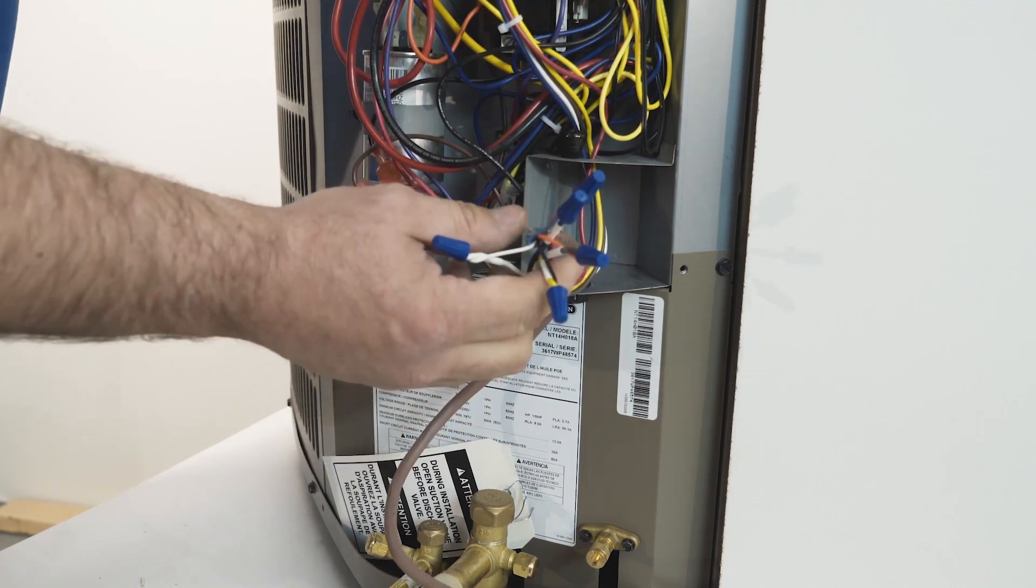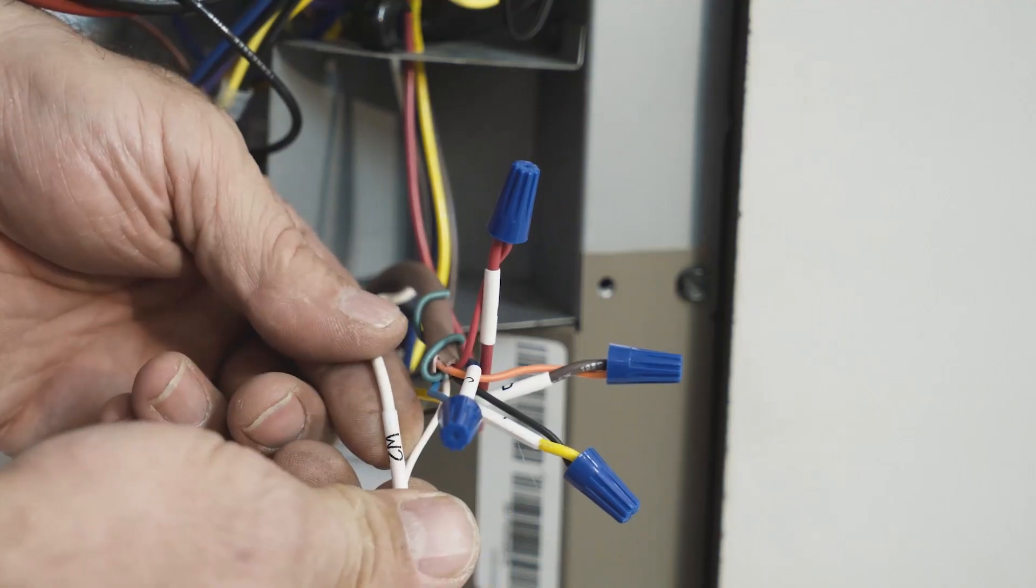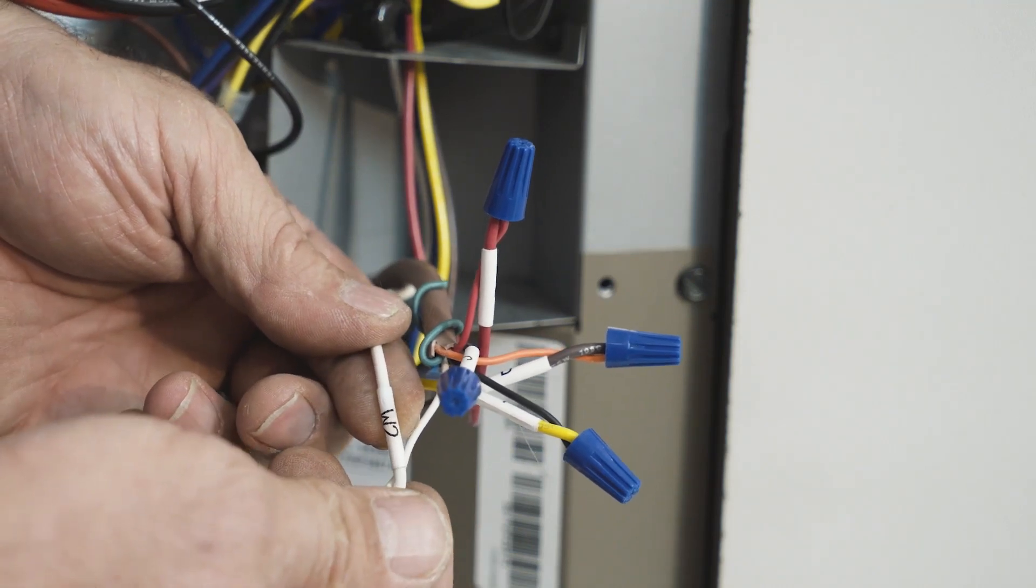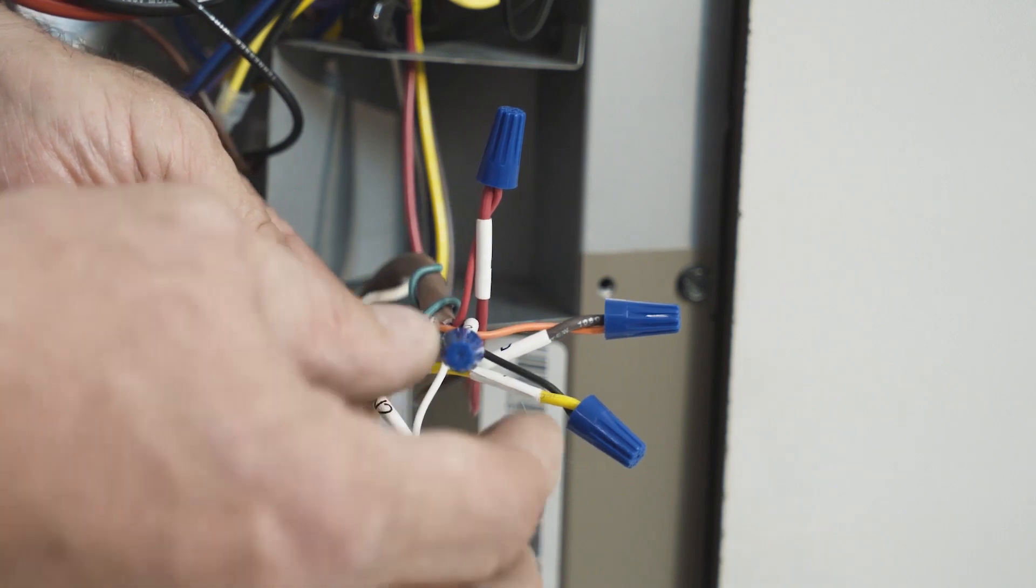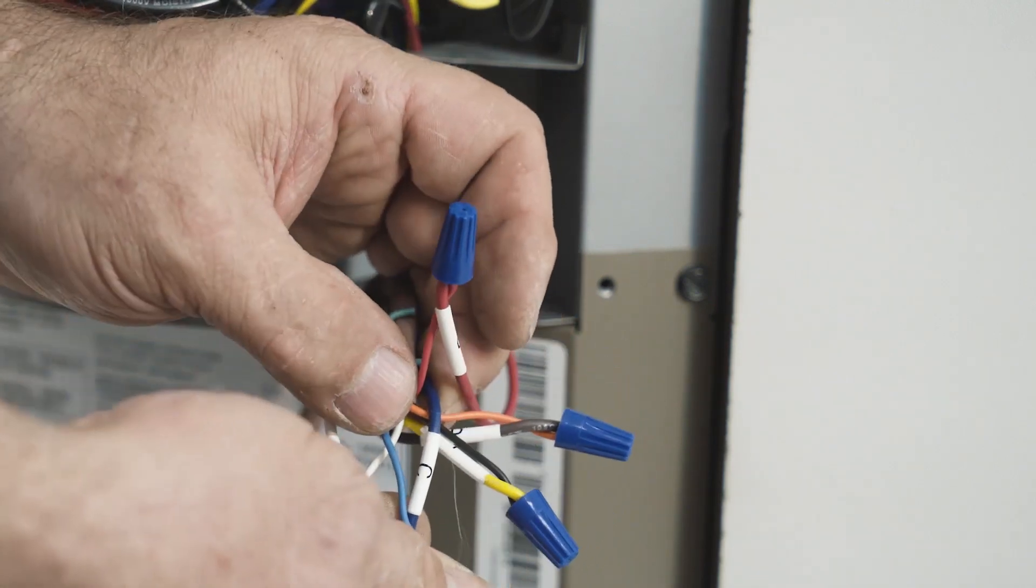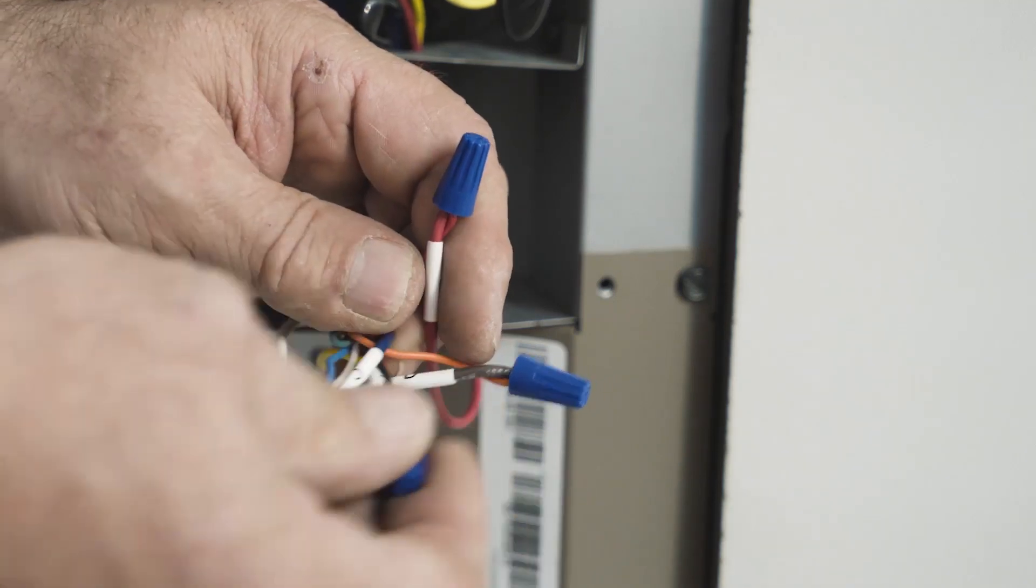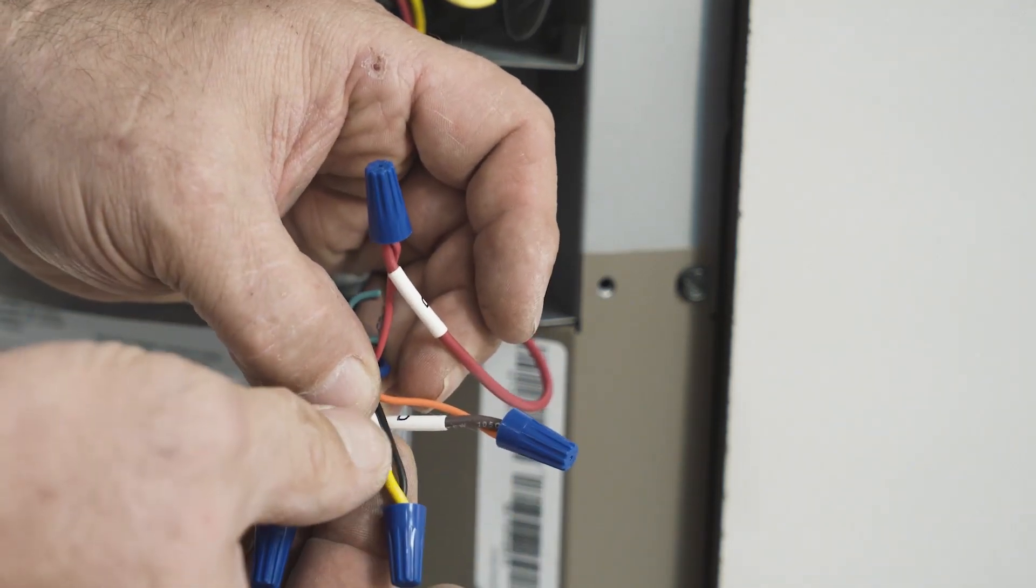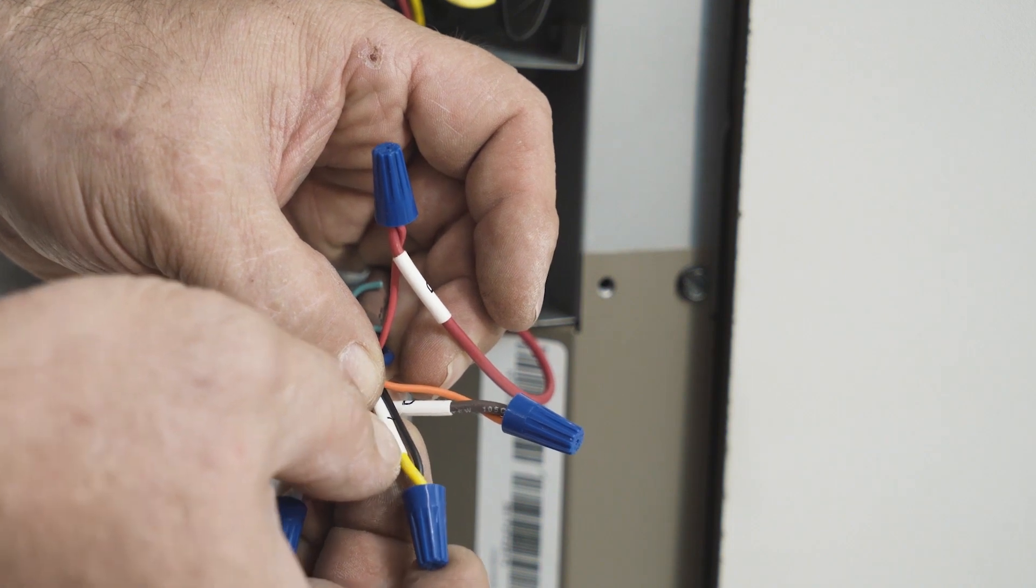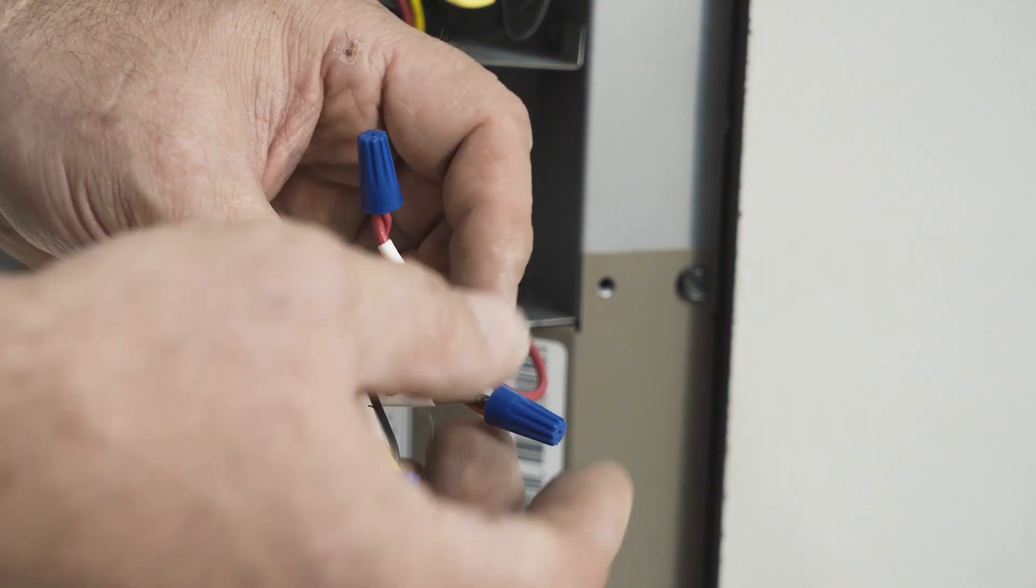Now we'll move on to the thermostat. The W2 wire is energized in the defrost cycle to bring on a call for heat if necessary. Common is a power feed to the control board. Y is a call for heating or cooling, basically going to bring on the compressor.